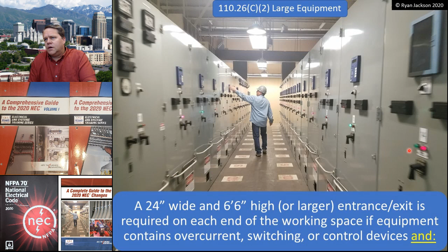There were other changes made in 110.26(C) which are much more substantial, however, and those have to do with large equipment in 110.26(C)(2). So the general statement here, and I think they put this in the code back in 1971, says for large equipment which is 6 feet wide or more and 1200 amps or more, a 24-inch wide by 6.5-foot high or larger entrance/exit is required on each end of the working space if the equipment contains overcurrent devices, switching devices, or control devices, and again is over 6 feet wide and 1200 amps or more.